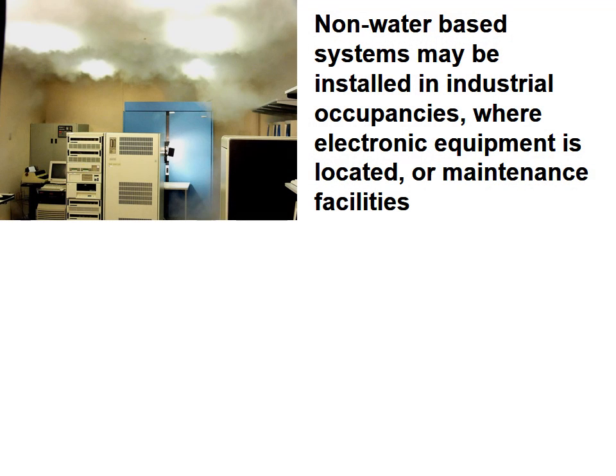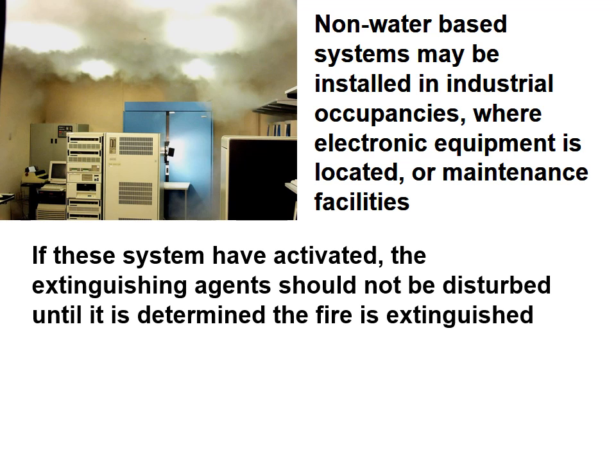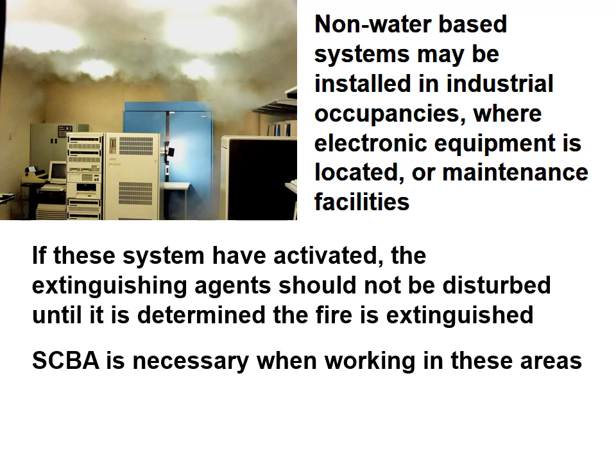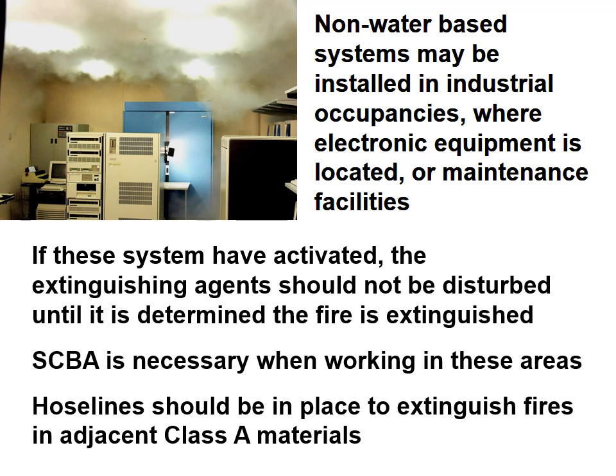A non-water-based system may be installed in industrial occupancies where electronic equipment is located, or in maintenance facilities. If these systems have been activated, the extinguishing agent should not be disturbed until it is determined the fire is extinguished. An SCBA is necessary when working in these areas. Hose lines should be in place to extinguish fires and in adjacent Class A materials.